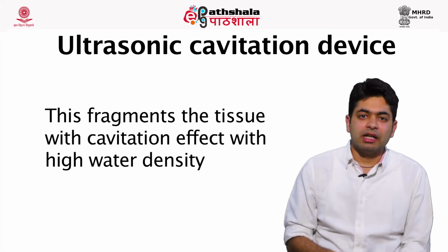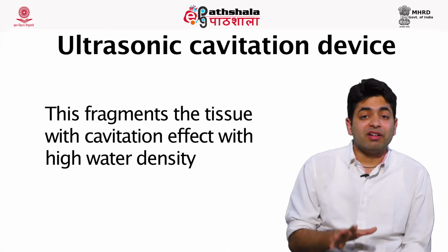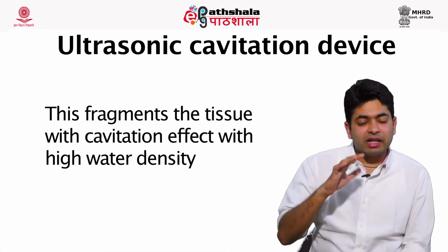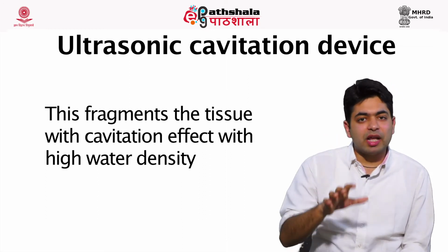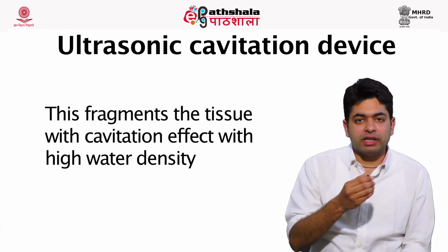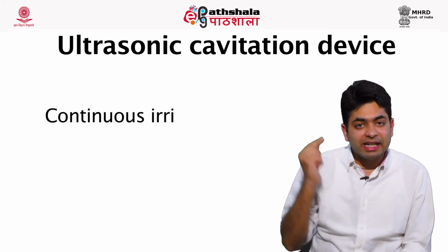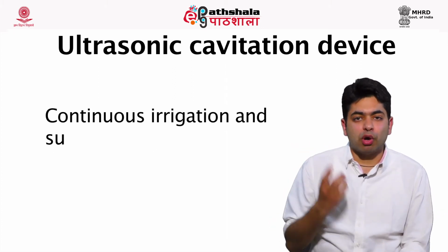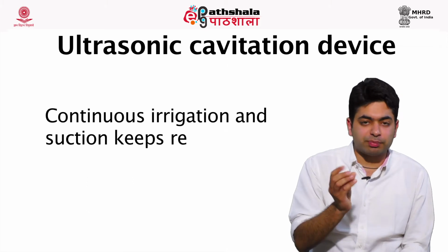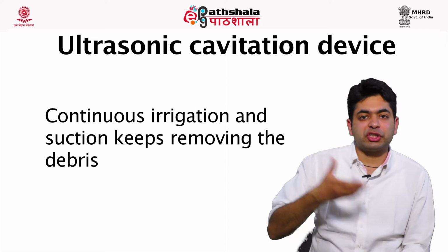Now the thing is, whenever a very fast oscillating tip hits the tissue with less protein density and high water content, with the help of the cavitation effect, that tissue is dissociated into fragments. It also has a continuous irrigator and suctioner. So what it does, that tissue is fragmented and water comes into it and it is suctioned back.